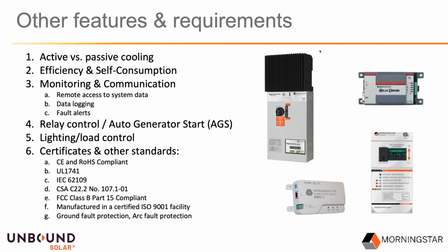Number 4 on this list is the ability to control a relay, or related to this, automatic generator start. Morningstar uses a relay driver accessory to be able to accomplish this. Sometimes, if there's an inverter in the system, your inverter might be able to control a relay, or there might be a separate dedicated auto gen start module from the inverter company.